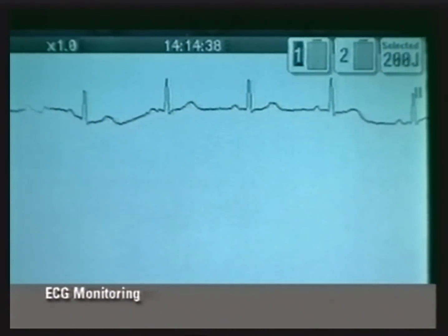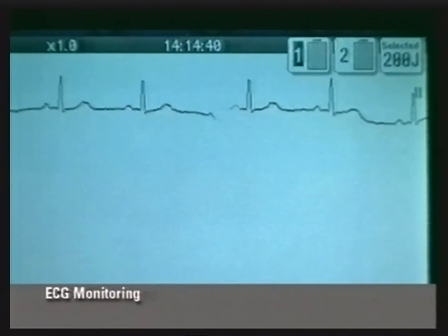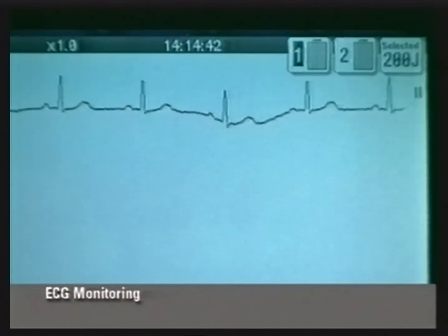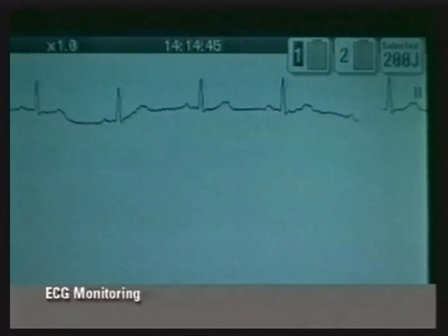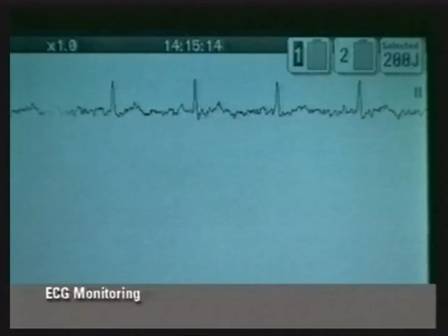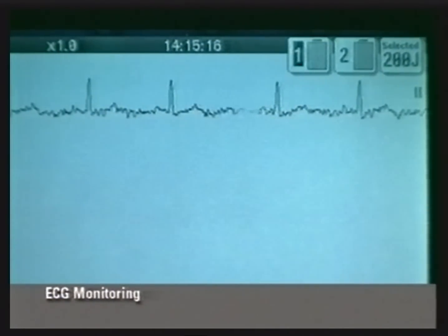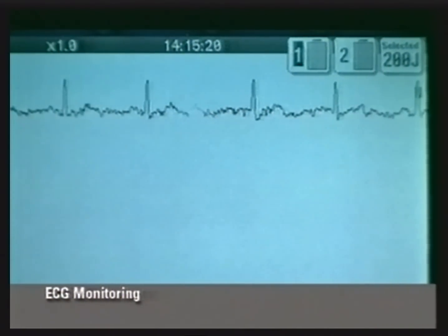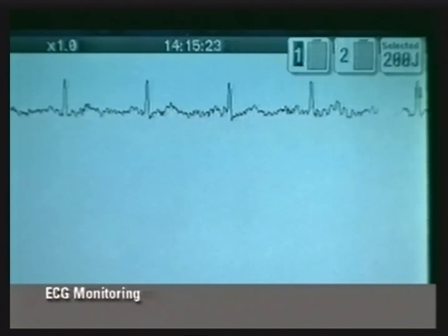Baseline wander may be due to the patient's breathing. This may be corrected by repositioning the ECG electrodes to an area with less movement. Two other reasons for poor ECG quality are using outdated electrodes and inadequate skin prep. Always use fresh electrodes and prep the skin as previously described.